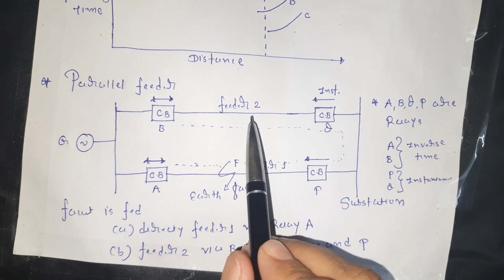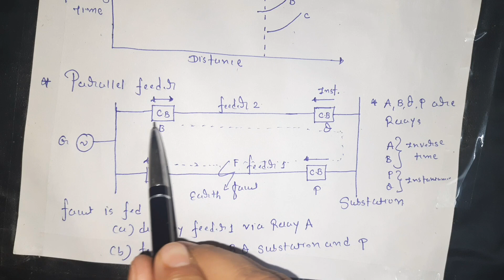This is the symbol of non-directional relay. This is the symbol of directional relay. This is feeder number 1 and this is feeder number 2, right? Now as you can see from the figure, parallel feeder can't be protected by only non-directional overcurrent relay, but we have to use non-directional as well as the directional relay for the protection of the parallel feeder.